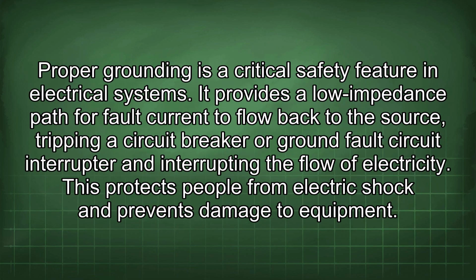Proper grounding is a critical safety feature in electrical systems. It provides a low impedance path for fault current to flow back to the source, tripping a circuit breaker or ground fault circuit interrupter and interrupting the flow of electricity. This protects people from electric shock and prevents damage to equipment.